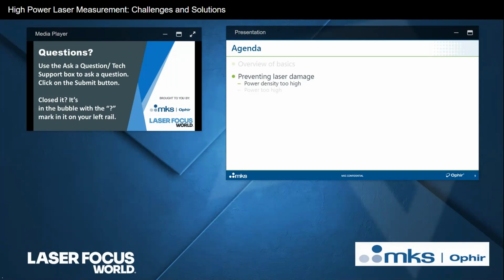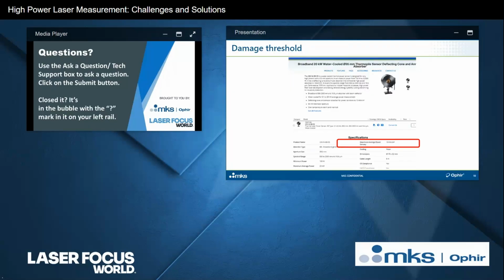So let's begin with power density being too high. That relates to one of the main parameters listed in any laser sensor's data sheet, and that's what's usually referred to as the damage threshold. By that I mean the maximum average power density, usually in kilowatts per square centimeter, the power incident per unit area.